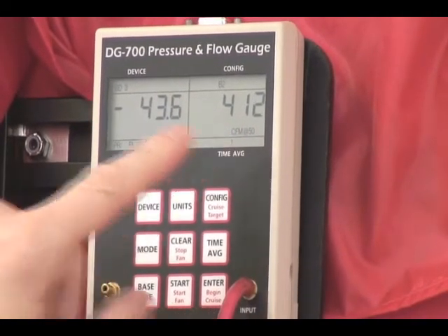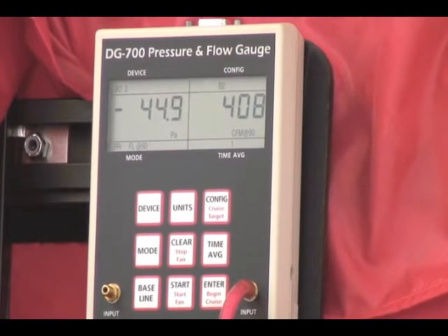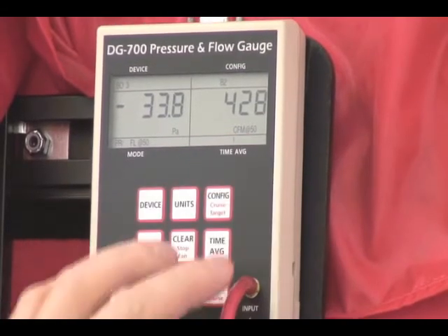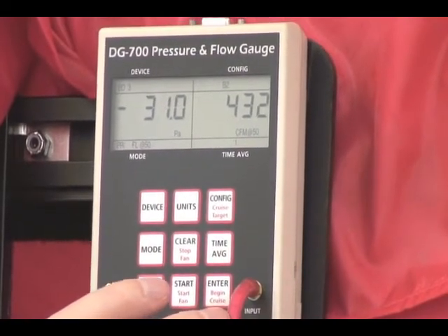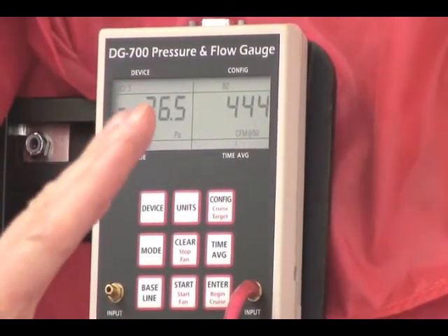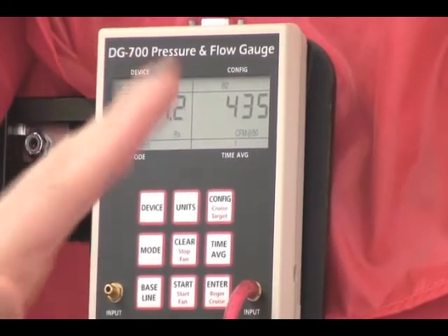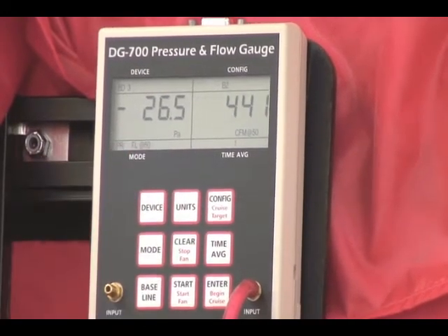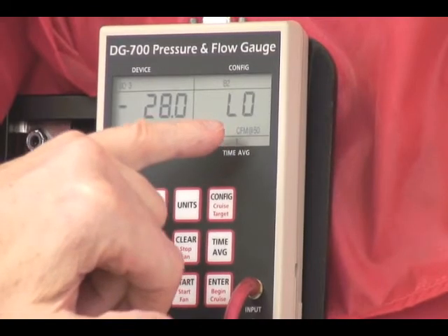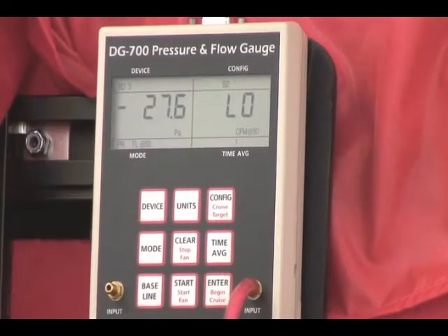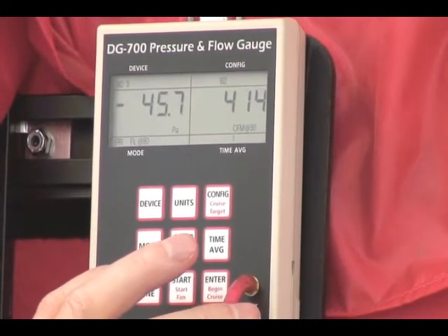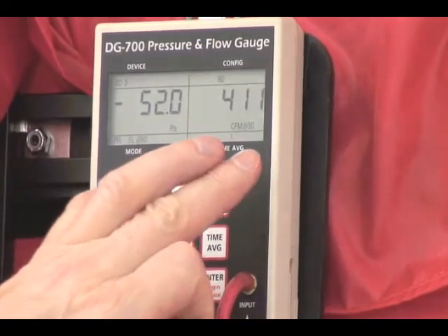415 CFM. So even if the pressure drops, as we're showing here, you'll notice that the CFM is not dropping very much, because it keeps extrapolating back up to 50 and answering the question mathematically, what would the flow be if I was at 50? So even though we're only at 27, we're still extrapolating back up to 50. The fan is running so slow now that our flow pressure is a little bit low. So let's speed it back up again. Notice again, the flow is not changing very much, because again, it's extrapolating to 50 pascals.